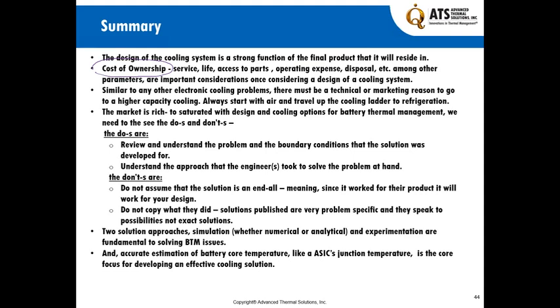Similar to any other electronics cooling problem, there must be a technical or marketing reason to go to higher capacity cooling. Always start with air cooling and travel up the cooling ladder to make sure you've exhausted the options associated with cheaper, less complicated systems like air cooling before going to liquid. And as we go from liquid to refrigeration, it gets that much more complicated.